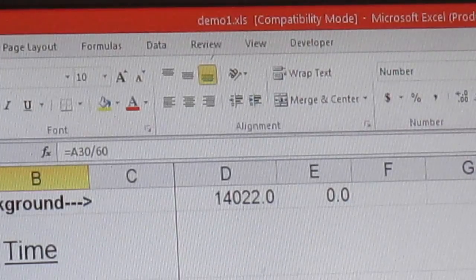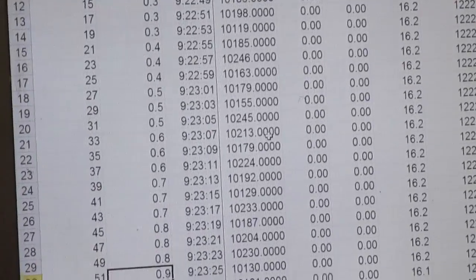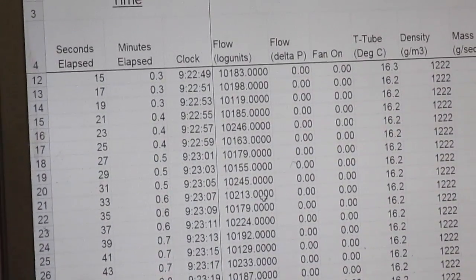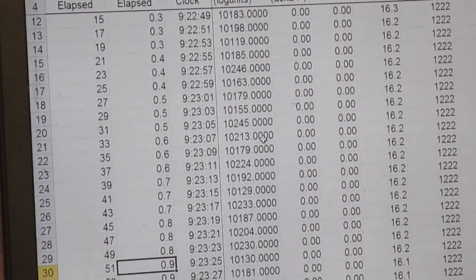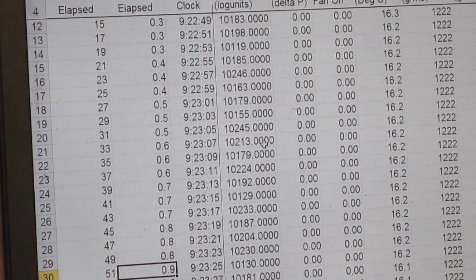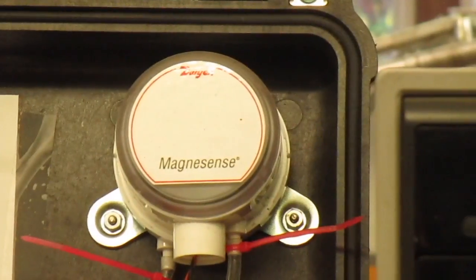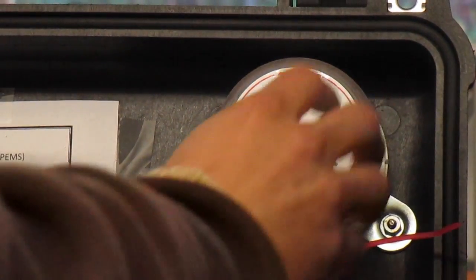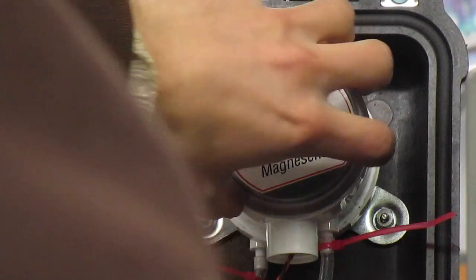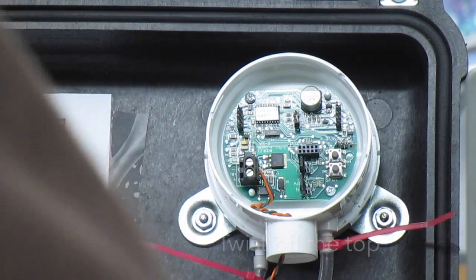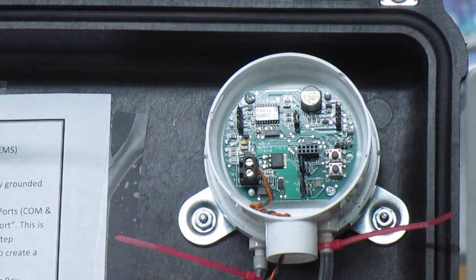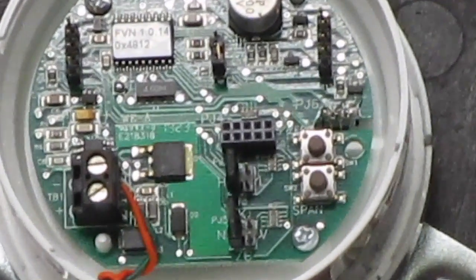So that's about right here. There's 0.9 minutes. There's logger data, D4. And the average is somewhere around 10,300. It differs depending on the MagneSense or sensor box that you have. And that can be zeroed. I'll show you that right now. It can be zeroed by pressing that top button.